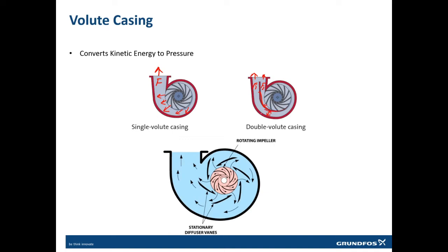So this will help to increase the life of the pump by reducing the radial forces. What are the radial forces? These are the forces on the impeller, on the shaft and on the bearings, because as I showed you, a lot of components are connected to this impeller. The life of all of these components will increase with this vane.